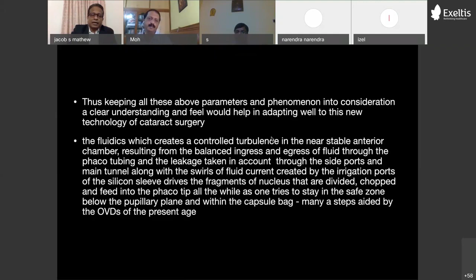So this is my own words. The fluidics create the controlled turbulence in the anterior chamber, resulting in a balance of the ingress and egress of fluid through the phaco tubing, with the leakage through the side ports and the main tunnel taken into account. Along with the swirls of fluid current created by the irrigation ports of the silicone sleeve, this drives the fragments of the nucleus that are divided, chopped, and fed into the phaco tip. All the while, one tries to stay in the safe zone, below the pupillary plane and within the capsule bag, so that your endothelium is protected as much as possible. The present OVDs help a lot in giving adequate protection. Even a decompensated cornea with a count of less than 1,000 cells can be operated upon very safely using this new procedure on one of the higher end machines with the use of the higher end OVDs.